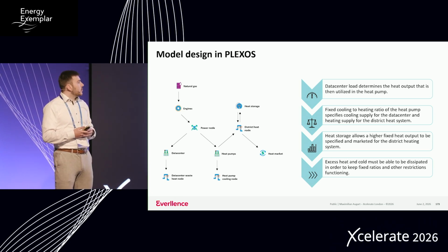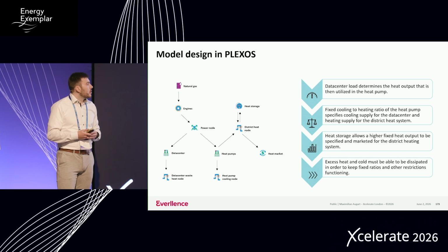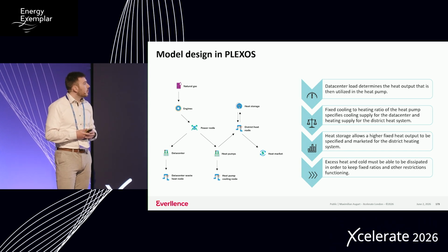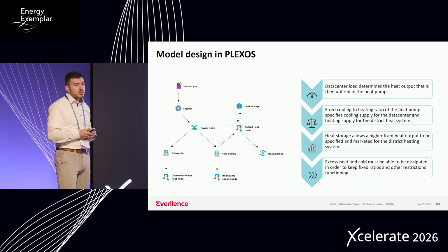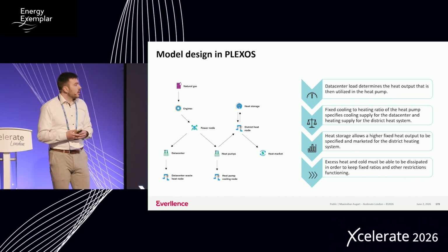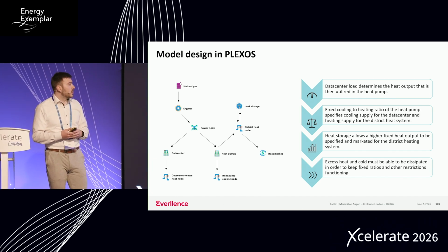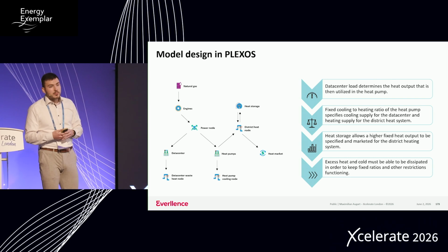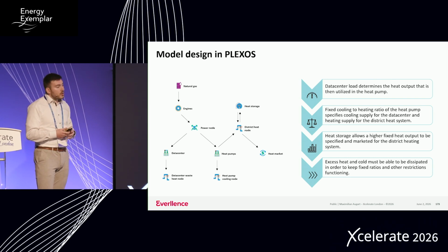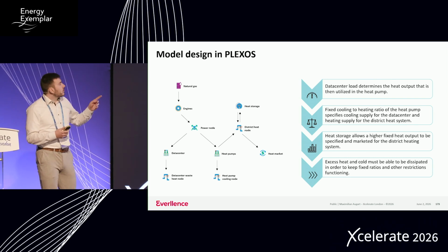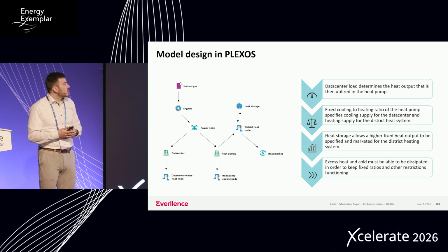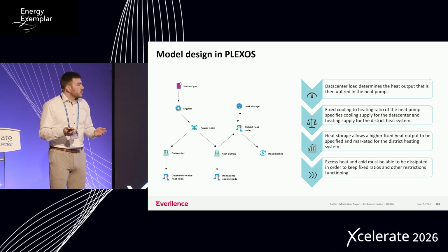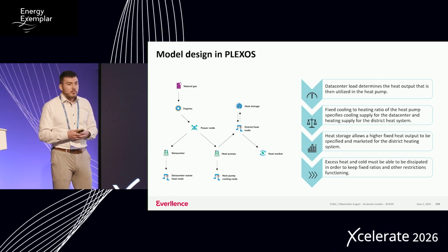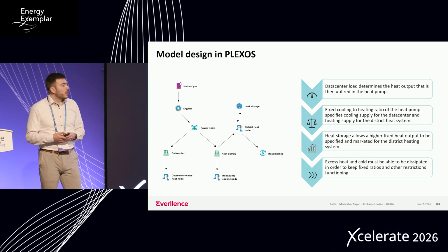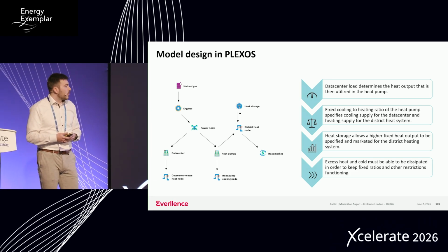I've got fixed cooling-to-heating ratios for the heat pump, so this doesn't change within the model. The heat storage allows a constant heat load output for the district heat system. You could also just use all the heat available from the data center into the heat pump as it comes - it depends on what your sink is working with.